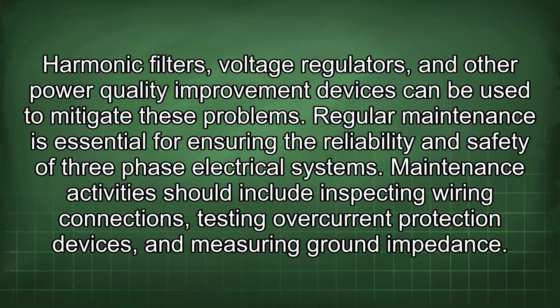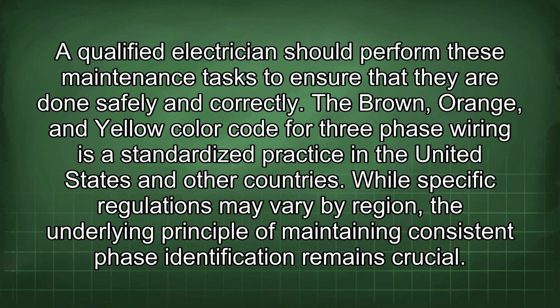Maintenance activities should include inspecting wiring connections, testing overcurrent protection devices, and measuring ground impedance. A qualified electrician should perform these maintenance tasks to ensure that they are done safely and correctly. The brown, orange, and yellow color code for three-phase wiring is a standardized practice in the United States and other countries. While specific regulations may vary by region, the underlying principle of maintaining consistent phase identification remains crucial.